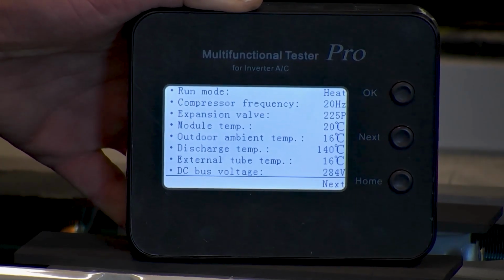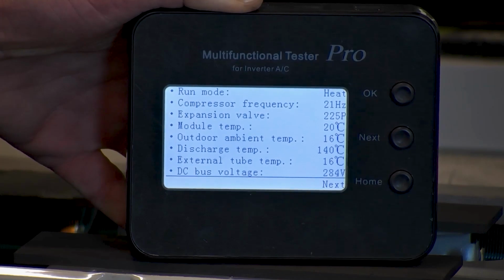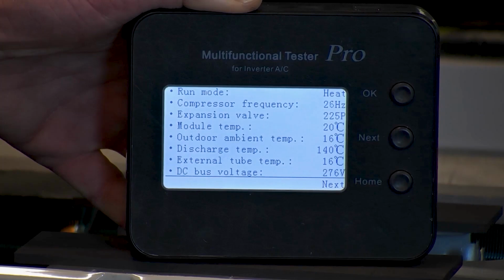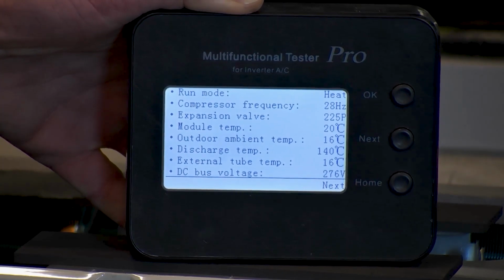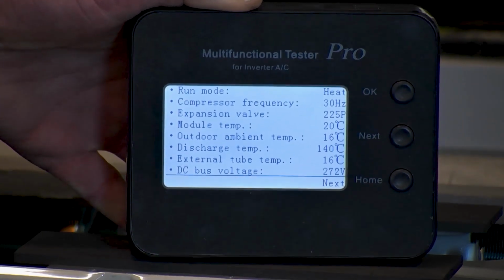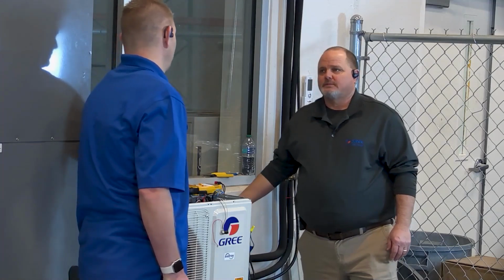It's giving compressor frequency, expansion valve step. Just turn the unit on. Module temperature, outdoor ambient, discharge temperature, external tube temperature, and DC bus voltage. All right, that's as far as I want to take it.